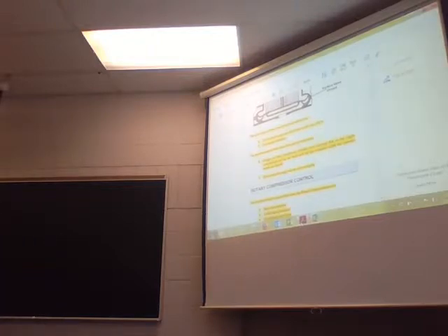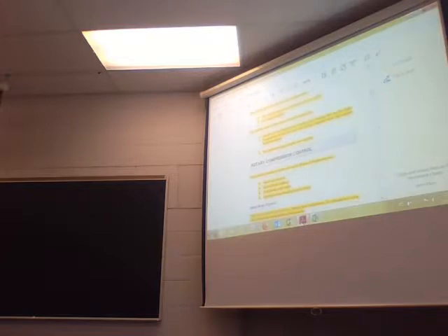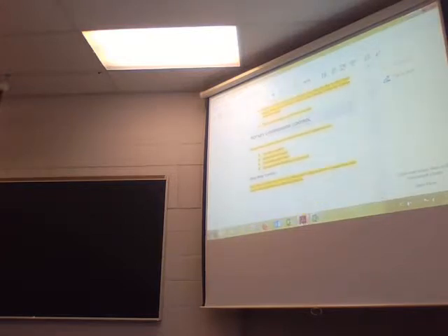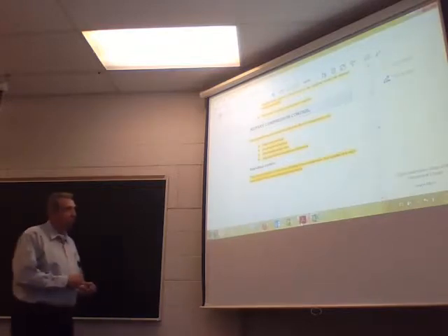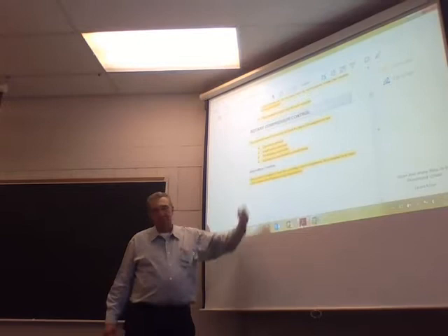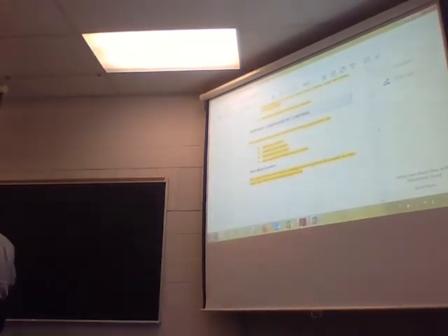All right. So now we're on rotary compressor controls: stop-start, load-unload, modulating air inlet, and microprocessor-based control system. These ones here you'll probably talk about more with Lori. Stop-start on a sliding vane compressor is similar to start-stop on reciprocating. Same idea. Pressure goes down, compressor starts, pressure goes up to your set point, it stops.